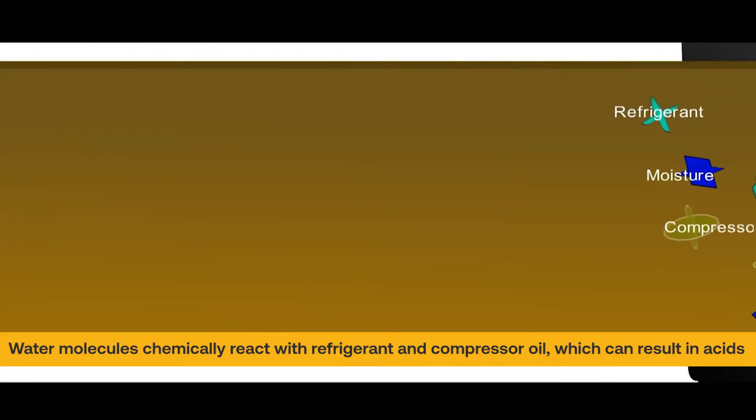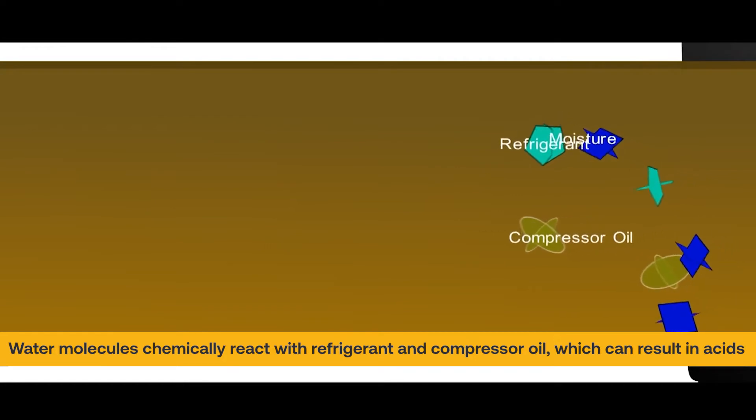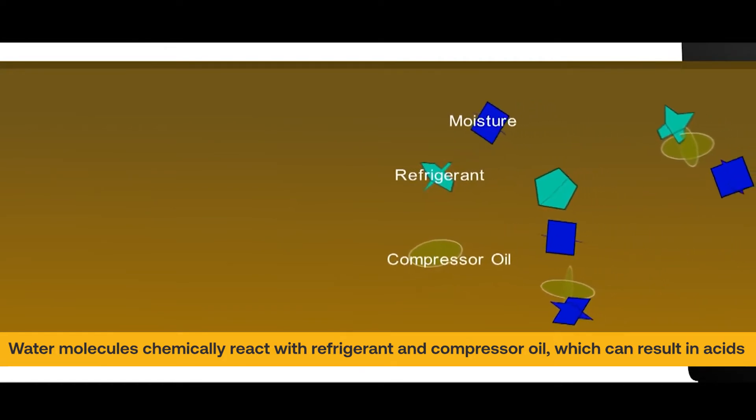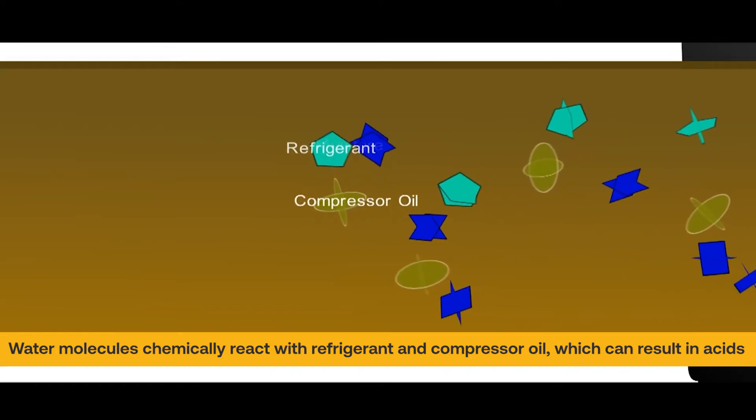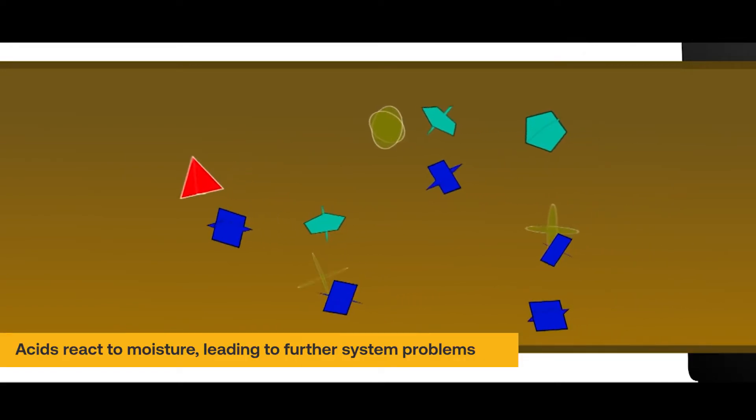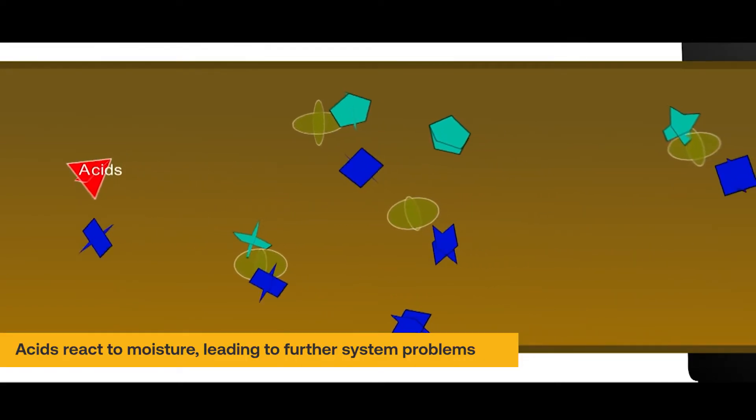Water molecules chemically react with the refrigerant and compressor oil, which can result in sulfuric, hydrochloric, and hydrofluoric acids. These acids then react with moisture, leading to further system problems.